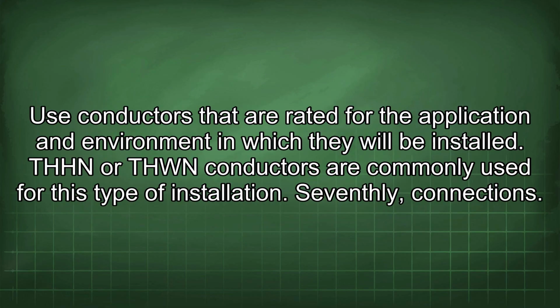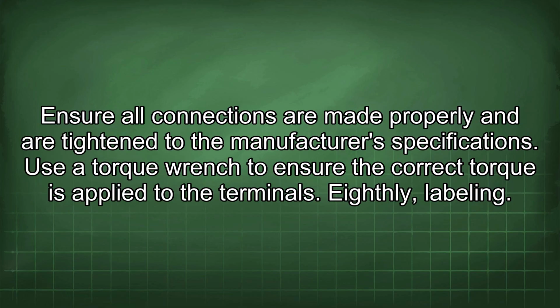Use conductors that are rated for the application and environment in which they will be installed. THHN or THWN conductors are commonly used for this type of installation. Seventhly, connections. Ensure all connections are made properly and are tightened to the manufacturer's specifications. Use a torque wrench to ensure the correct torque is applied to the terminals.